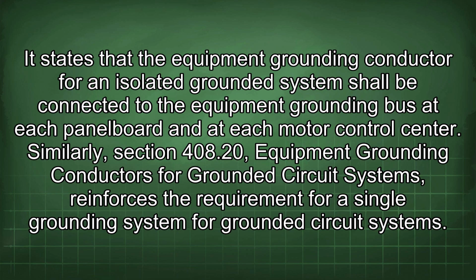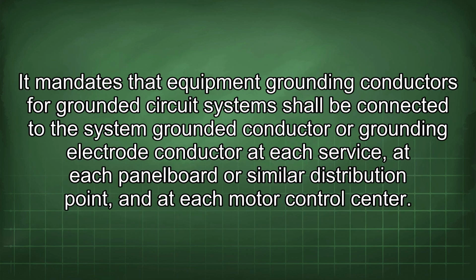Similarly, Section 408.20, Equipment Grounding Conductors for Grounded Circuit Systems, reinforces the requirement for a single grounding system for grounded circuit systems. It mandates that equipment grounding conductors for grounded circuit systems shall be connected to the system grounded conductor or grounding electrode conductor at each service, at each panel board or similar distribution point, and at each motor control center.